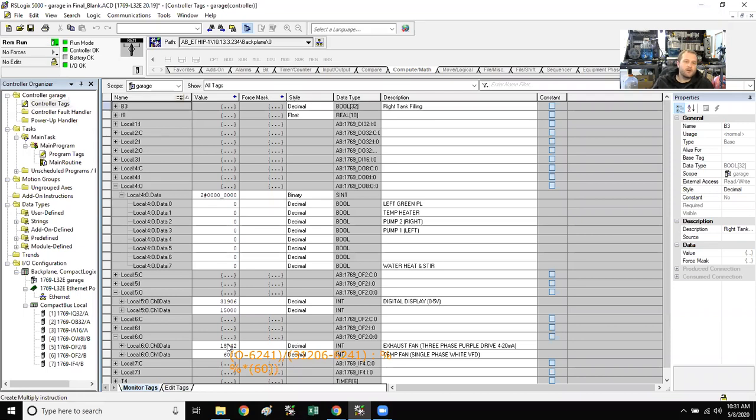Yeah, but what if that number changed to 19,503? Then I would have to redo it. No, you don't. Our output wouldn't change. It's the same output. If we just put in our logic, hey, take the output on channel 0 and run it through this formula, no matter what that number is, it'll always show you what the fan speed is, right? Oh yeah, I could just plug in the actual channel. Yes. I forgot about that. All right, so just plug in channel.